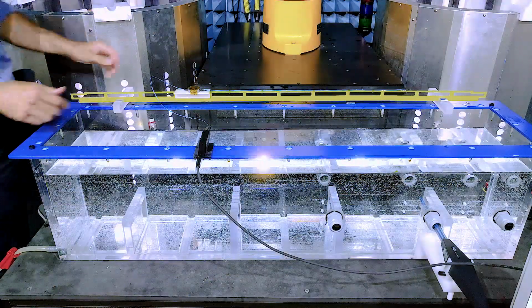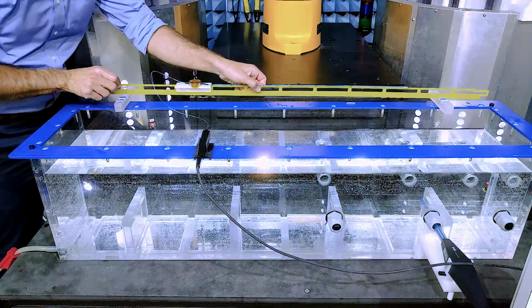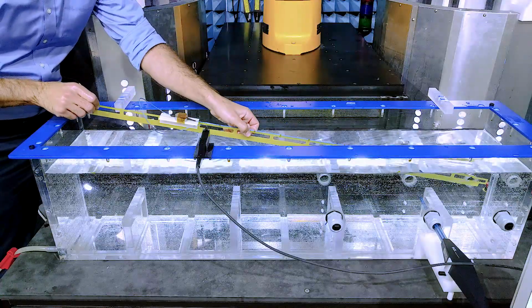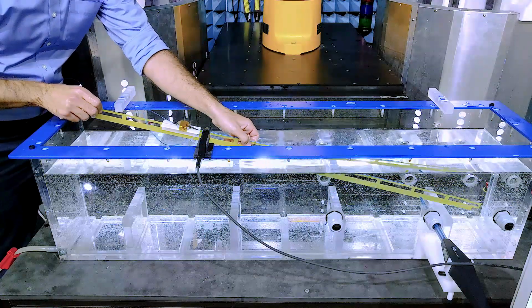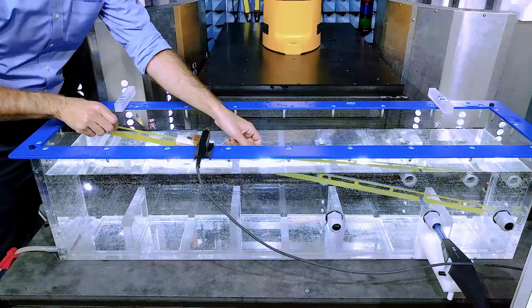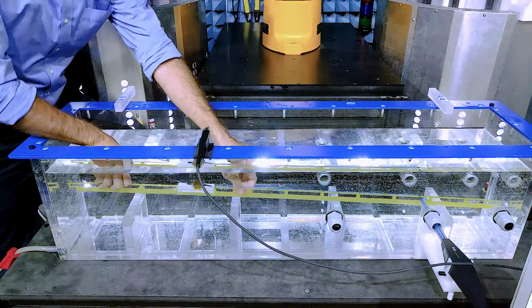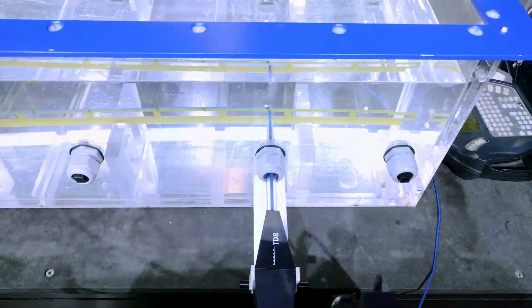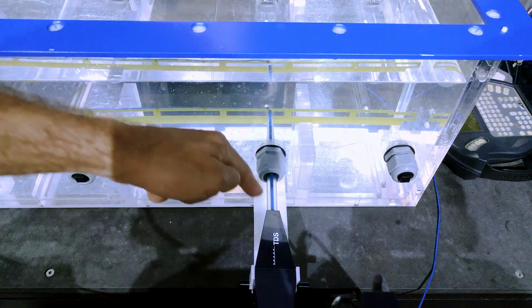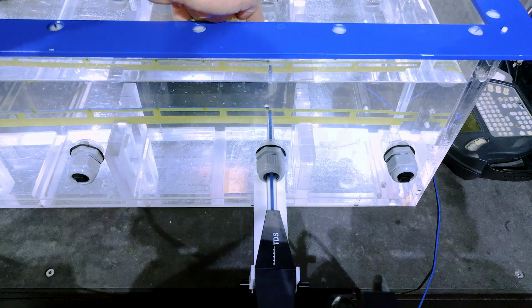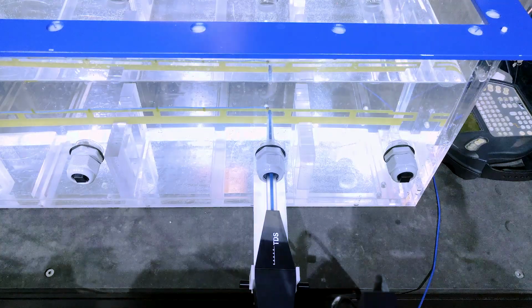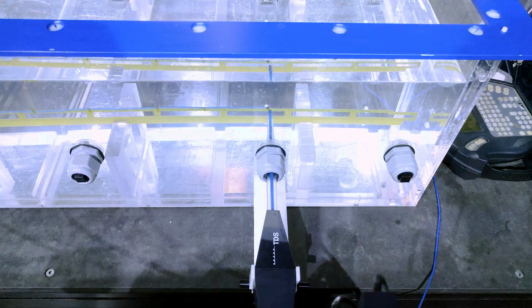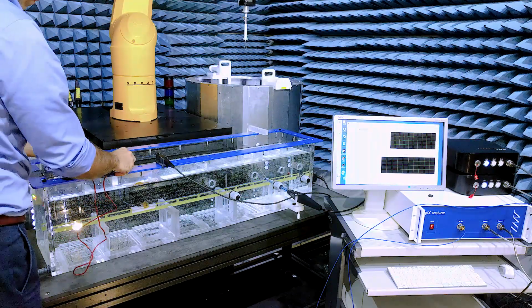Now we can put the racetrack inside the phantom, which is filled with the tissue simulating liquid. Here we have to avoid bubbles collecting in the area of the electrode around the implant. It can help to tap on the racetrack or to put the implant in and out of the water a couple times. This is a fiber optic time domain sensing, or TDS, E-field probe. You can see that the implant is lined up with the TDS probe that measures the electric field at the tip. Don't forget to check the conductivity and temperature of the liquid.